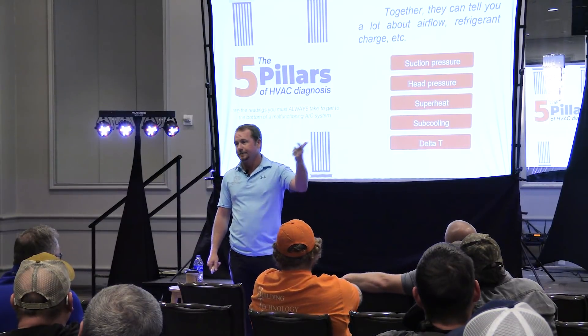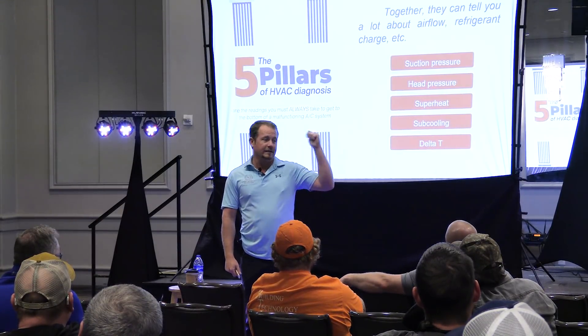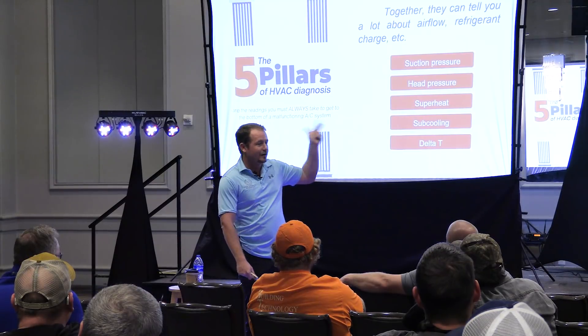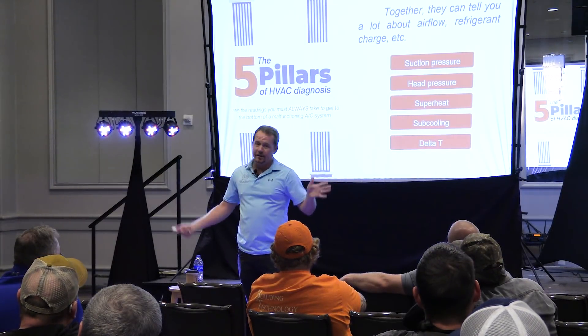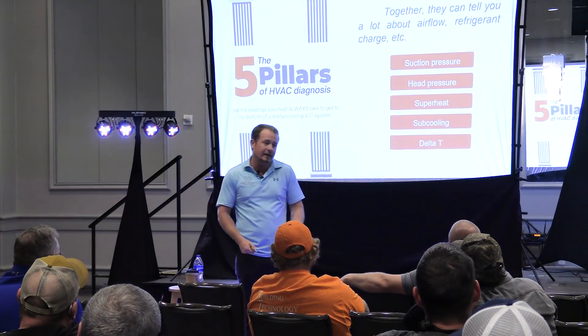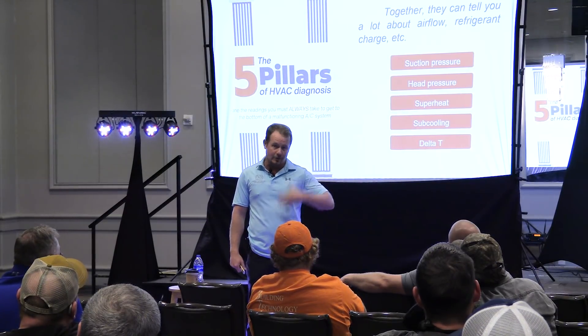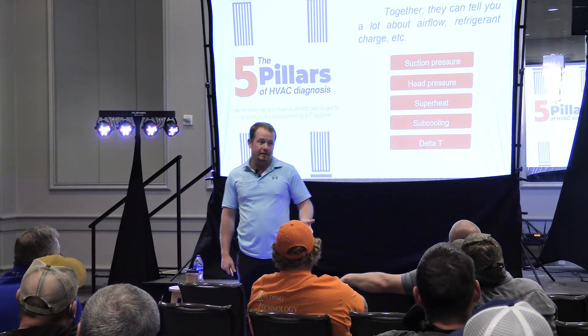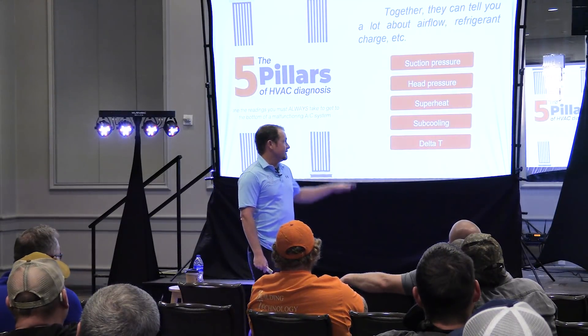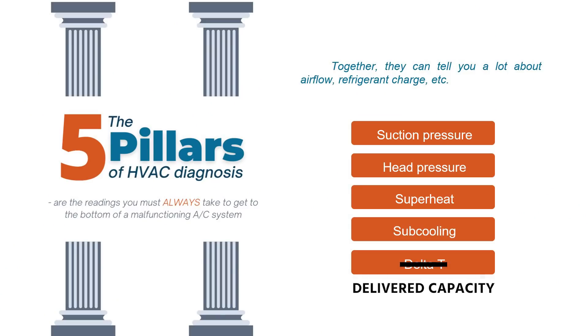If you use MeasureQuick and good psychrometers — Fieldpiece, Testo, UEI probes that are reasonably new and not gummed up giving bad readings — you'll get a pretty good idea of how the system's operating in terms of BTUs, almost as easily as measuring a delta T. So nowadays you could take this list, eliminate delta T, and put delivered capacity in — total BTUs removed, total BTUs added by the equipment — and it would be a much better actual look at system performance.